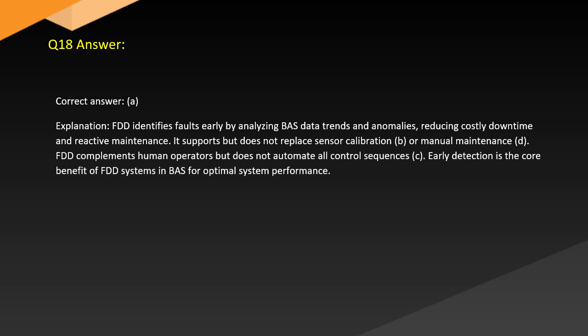FDD identifies faults early by analyzing BAS data trends and anomalies, reducing costly downtime and reactive maintenance. It supports but does not replace sensor calibration, B, or manual maintenance, D. FDD complements human operators but does not automate all control sequences, C. Early detection is the core benefit of FDD systems in BAS for optimal system performance.